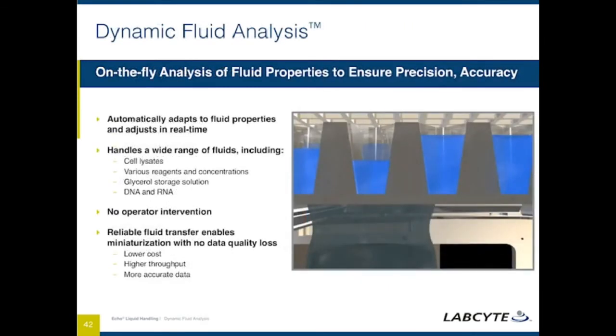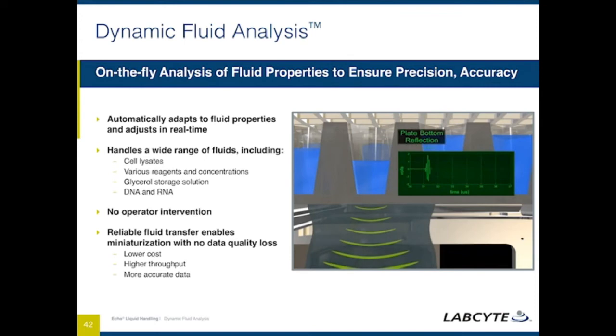As I mentioned earlier in my presentation, dynamic fluid analysis is proprietary to Labcyte and has the unique benefit to the customer that it automatically adapts to fluid properties within the well and adjusts in real time as it's doing the transfer. It borrows from medical ultrasound as well as sonar. And if we view the video here, what you can see is that there is a low energy ping that's being emitted by the transducer. It's reflecting off three surfaces. First is the bottom of the plate, the second is the bottom of the well, and the third one is the surface of the fluid.